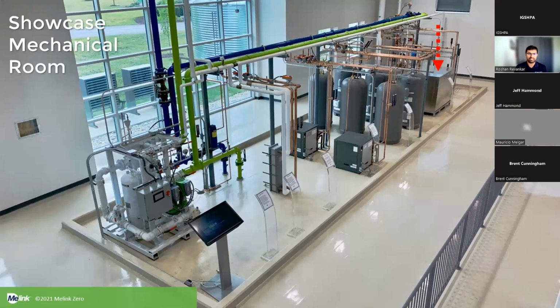How we do that is we've identified items in the building that consume energy that are not needed at certain times of the year. So if we see that in the peak of winter or peak of summer, we are closer to hitting the 50 kilowatt limit, then we start to turn off systems and not use energy consuming devices and go back to using other thermal energy storage that may consume lesser energy at that time. So what the thermal energy storage system lets us do is be able to move and shift the load as and when we want to meet the demand.